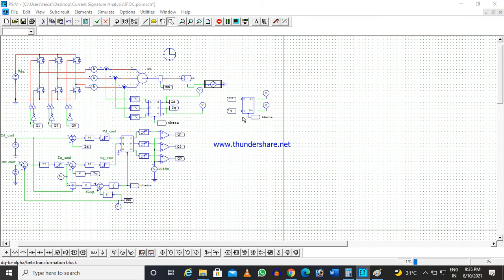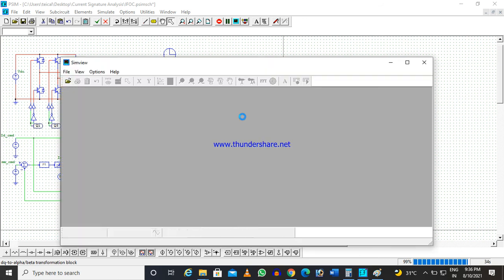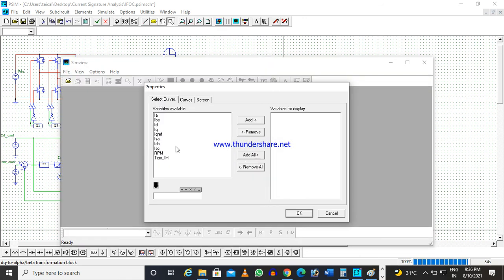So here the question is that the data logger or the ADC you will be using to capture the time domain data should be high resolution, okay, otherwise you cannot. If the severity of the vibration or the fault is small, and the resolution of the ADC or data logger is not sufficient, you will not be able to catch the peak. It will be there, but you will not be able to see it prominently.